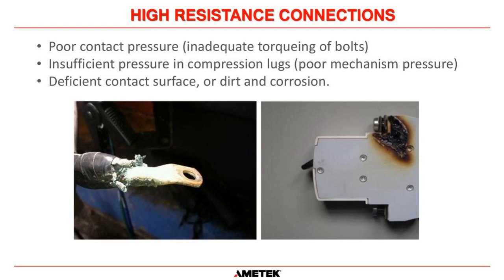And the other one is deficient contact surfaces, either dirt or corrosion or something else between the contact of two electrical conducting surfaces. And you can see once again in that picture on the left that there is some green corrosion, probably caused by water ingress into that system. And once that corrosion builds, you can see it here. If that corrosion was found on this surface, then that would cause a high resistance connection between that lug and the mechanical surface of what it's being connected to. And that can cause high resistance.